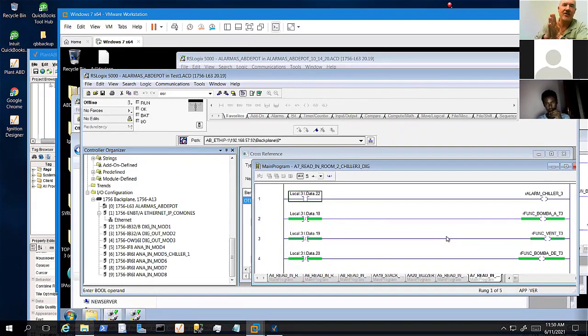Here's the other problem. I don't know if any of you do Allen Bradley, but Allen Bradley has many versions of firmware, and your software has to match the firmware. This is a version 20 PLC. Version 20 is a funny deal - it was in between the old ControlLogix, which was version 8 through version 19 or 20, and then there's the new one, which is Studio. Studio is version 21 and part of 20, through about 33 right now.